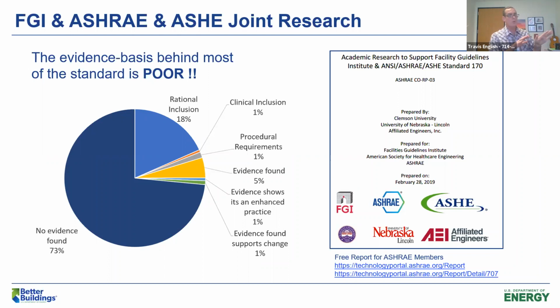So, long story short, Kaiser Permanente has elected not to follow the air change rules in our clinics and medical office buildings. We do not voluntarily adopt ASHRAE Standard 170 anywhere we're not required to by code, and that's fundamental to this project. The building we're talking about is a clinic - a big clinic with variable volume systems and a return plenum. If we were following the air change rules, the energy performance we're talking about would flat out not be possible.